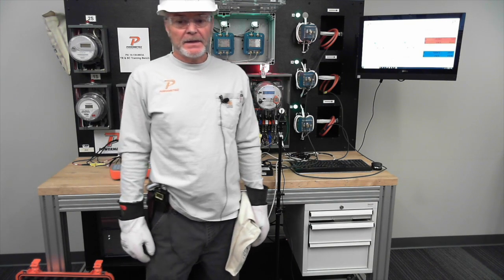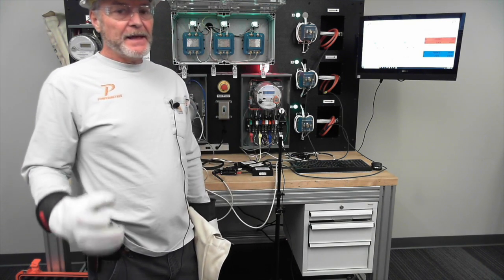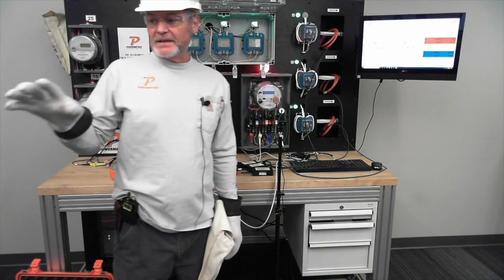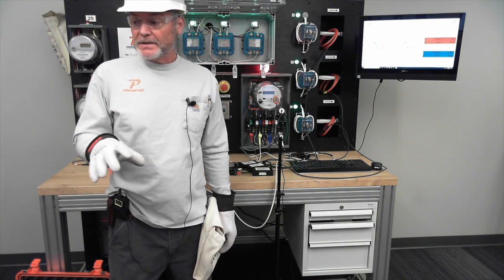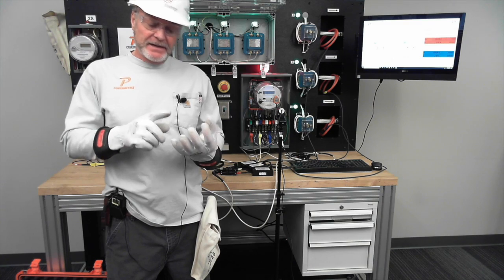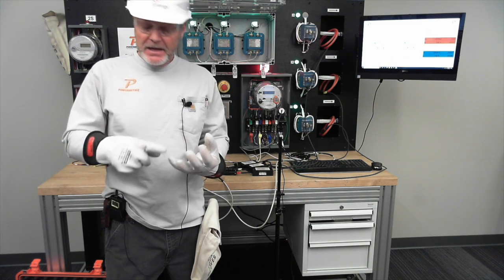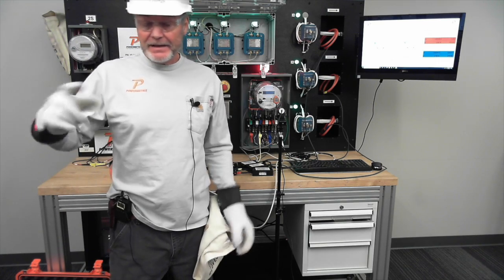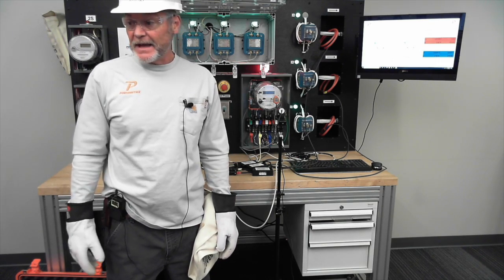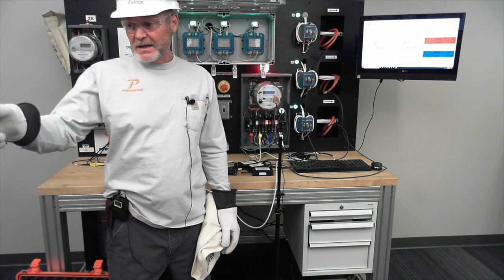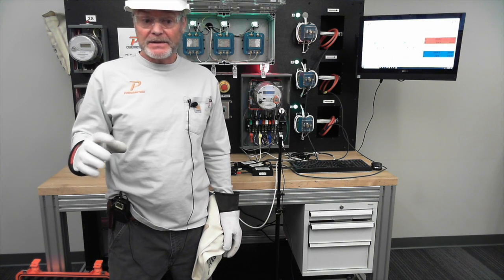So you can see that using all of these secondary probes and some primary probes can really help you out in the field if you've got distances to conquer. If you've got a situation where they run multiple conductors through, you're going to need to figure 8 and use those flexes for that. But you've got these secondary and even some primary clamp-ons that are great.